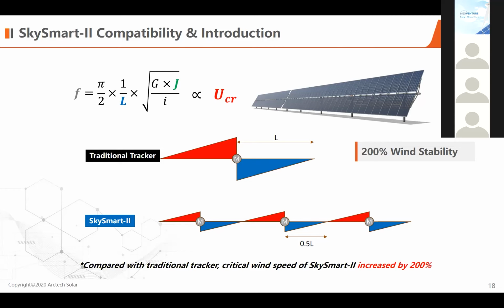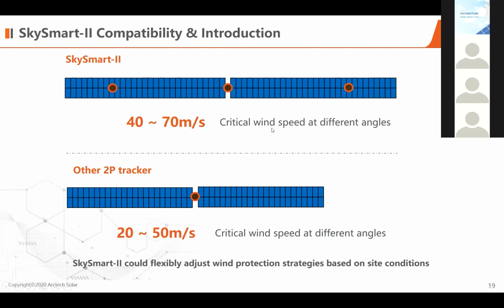So when we compare to the traditional tracker under the critical wind speed, the SkySmart 2 trackers will increase the wind stability by about 200%. And also, the SkySmart 2 critical wind speed can withstand more than 40 meters per second, even up to 70 meters per second. But other tracker solutions only withstand about 20 to 50 meters per second. So when we choose the SkySmart 2 solutions, it can be more flexible to adjust the wind protection based on different site conditions.